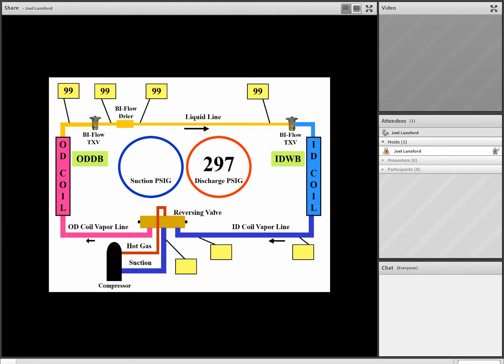So we should have 10 to 15, but we have 31, so our subcooling number is high. So in our example, we have too much liquid in the outdoor coil for whatever reason. Now remember, team, we'll find out what those reasons are later. Right now, we're just looking at subcooling in a practice session. So our subcooling is high in this example. That tells us that the warm coil is flooded.